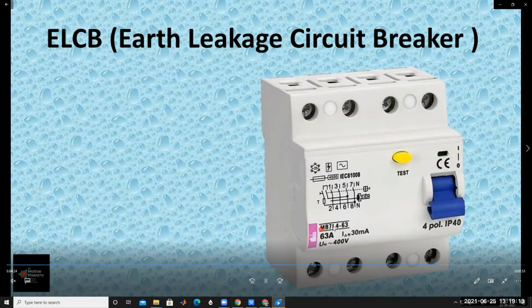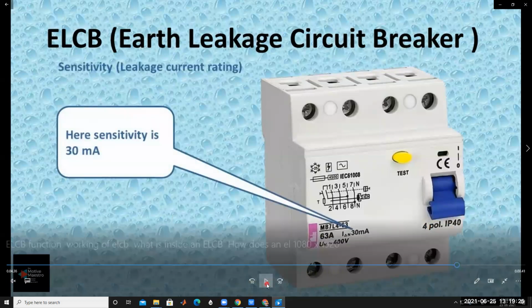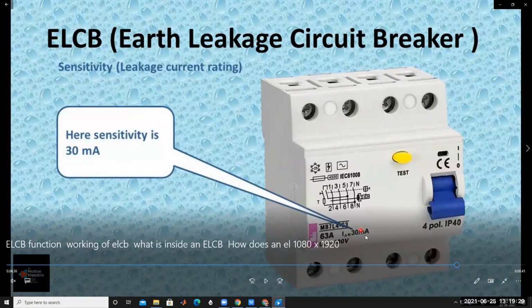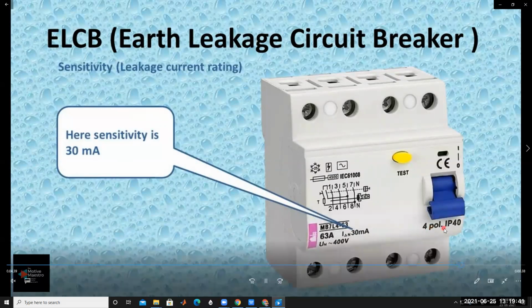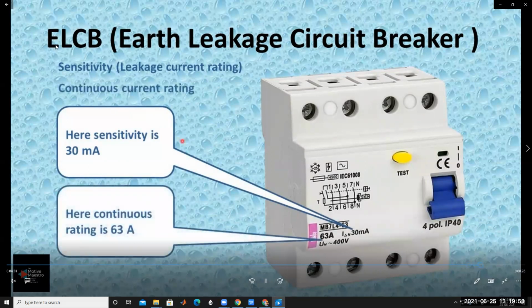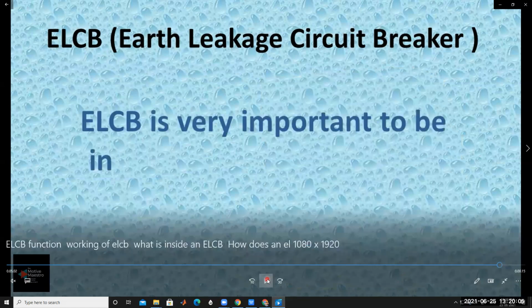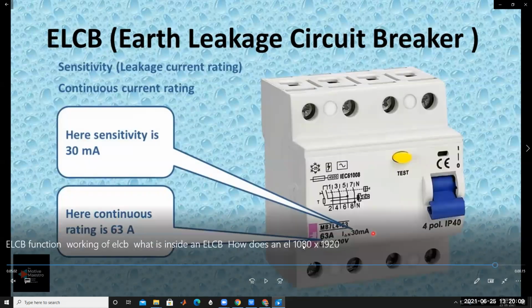Here the operating current of this ELCB is 63 amps, with a 400 volt rating. This is called a 4-pole ELCB. The sensitivity of this earth leakage circuit breaker is indicated like this: here the sensitivity is 30 milliamps. And it is a 4-pole circuit breaker, so 1, 2, 3, 4 poles. So this is about the ELCB circuit breaker. The continuous current rating of this ELCB is 63 amps, and the sensitivity rating is 30 milliamps.